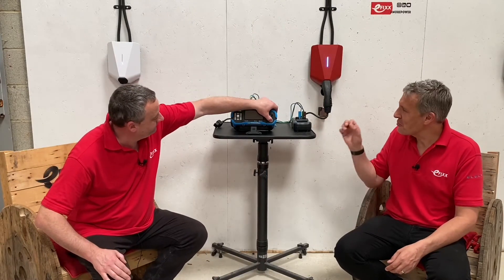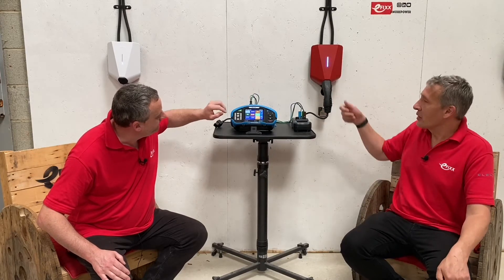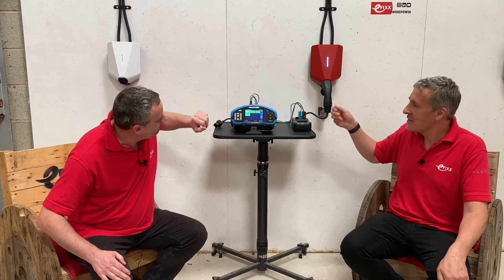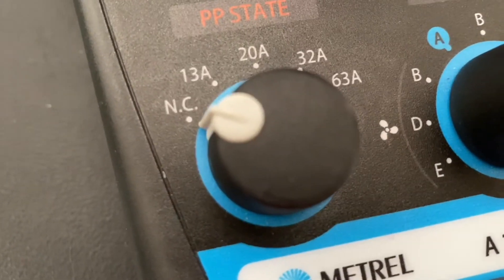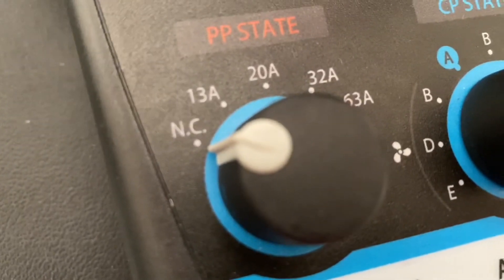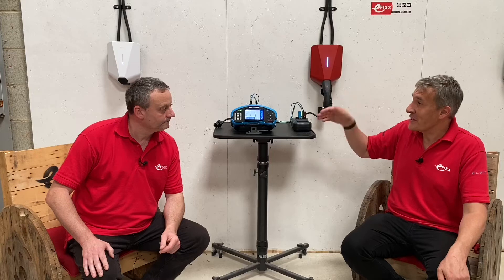Gordon, you think you've got a hack to test an easy EV charging point for its RCD test. Well, what I found during the test is that because of the unique way the Easy charger resets itself by pulling in and out of the charge lead, we can simulate that using the NC function on the PP state of this EV adapter from Metrel. So it will basically do the whole test without us doing anything.